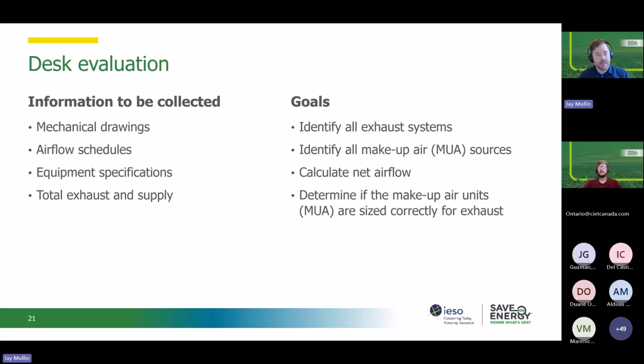using those ratings to calculate the net airflow, and at that high level, just based on nameplate, determine if you have enough makeup air unit capacity, if that's sized correctly for the exhaust, or vice versa. Do these balance out just at the nameplate level, or are there significant differences? This can happen: facilities expand, you bring in new pieces of equipment, add new exhaust to treat those processes, and sometimes facilities don't add additional makeup air units for that, so you can get this imbalance even just on paper. So it's good to understand that.